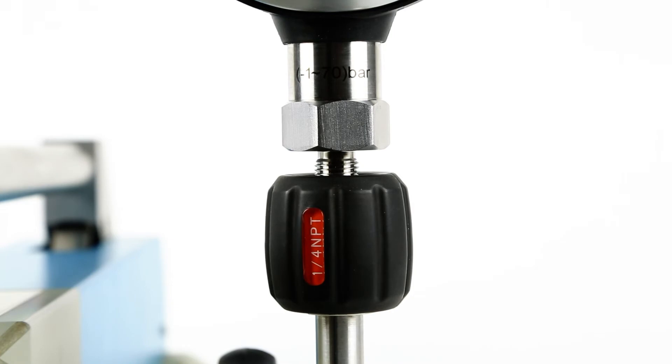Save time with Additel's hand-tight NPT or BSP quick connectors that do not require any tools or thread sealant for leak-tight operation. Simply connect your reference gauge or unit under test and you're ready to calibrate.